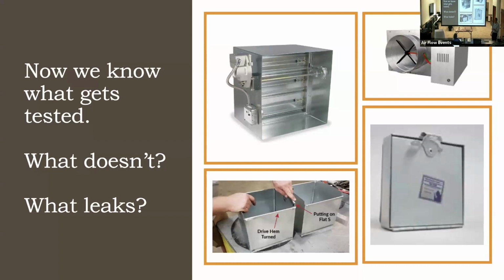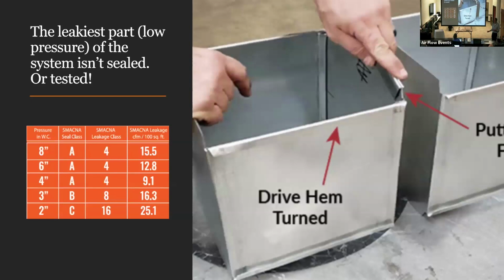So who knows what this is? Fire smoke damper, terminal box, access door. We talked about the low pressure ductwork, right? What leaks, what doesn't? All right. Now, again, how do we test low pressure ductwork? Don't. What? We don't? We don't. So how do we actually know if the low pressure ductwork leaks?